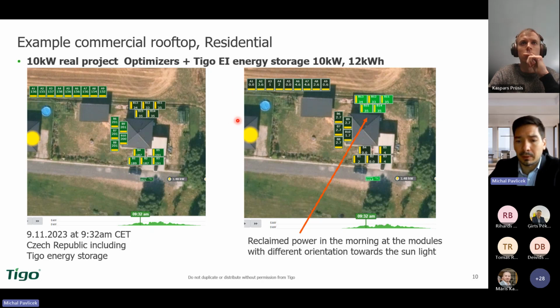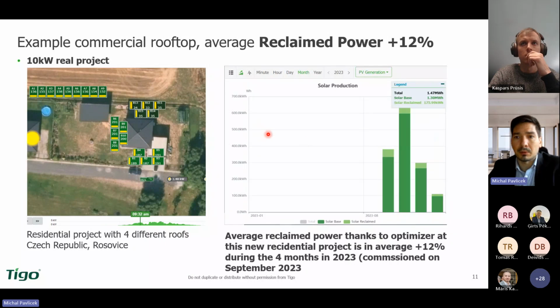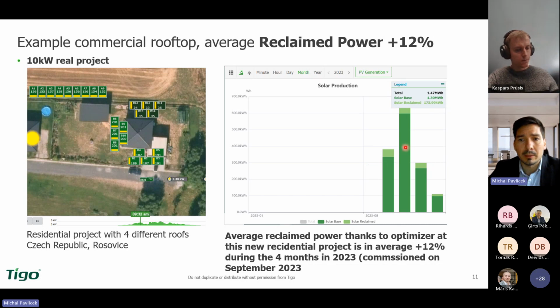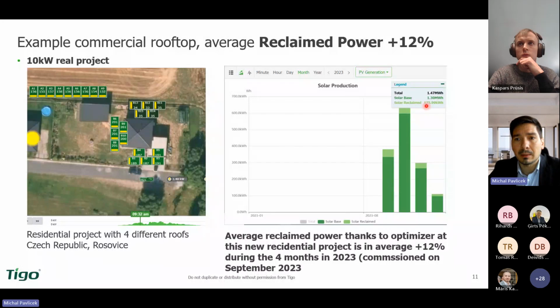In fact, it is also using our inverters with energy storage, 12 kilowatt hours. So we will show also some features there. You may see, if you look at the last 4 months, because the project had been started just in September, so it's only 4 months in operation. And in fact, if you calculate this light green, which is the additional power reclaimed from the optimizers, compared to the dark green, which is the power of modules without optimizers, you may see from the numbers that the average reclaimed power from these 4 months is 12%.